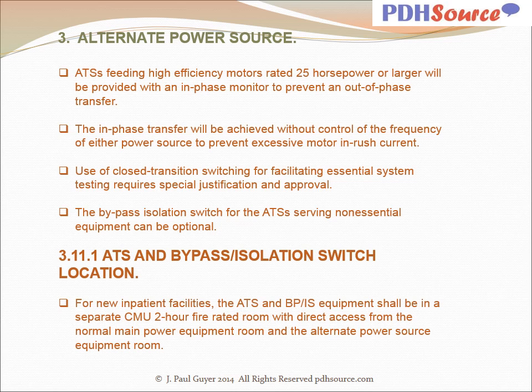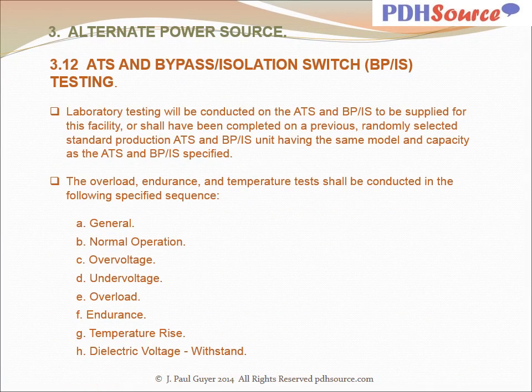With regard to ATS and bypass isolation switch location, for new inpatient facilities, the ATS and bypass isolation switch equipment shall be in a separate CMU 2-hour fire rated room with direct access from the normal main power equipment room and the alternate power source equipment room. Laboratory testing will be conducted on the ATS and bypass isolation switch to be supplied for the facility, or shall have been completed on a previous randomly selected standard production ATS BPIS unit having the same model and capacity as the ATS and BPIS specified.